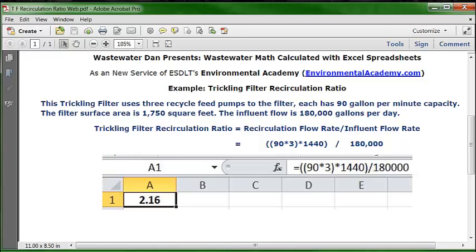We do need to use multiple parentheses for the recirculation flow rate part. We've got three pumps, each with a capacity of 90 gallons per minute, so that's where the 90 times 3 comes in — that gets the flow rate for all three pumps in minutes. Then we convert from minutes to days by multiplying by 1,440, which is the number of minutes in a day. So we have open parentheses twice, then 90 times 3, then close parentheses, times 1,440, then close parentheses for the entire top side of the formula.